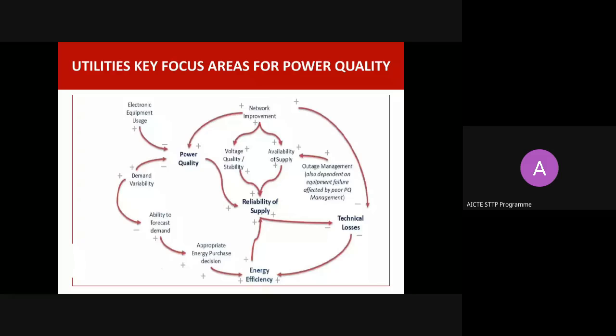There is transmission loss and distribution loss, put together as T&D loss. In current practice, we call it AT&C loss, aggregate technical and commercial loss. All the losses we are grouping into technical and commercial. In India, it is now less than 21%. In those days, it was more than 25%, 27%. On an average, it is about 21 to 23%. In Tamil Nadu, it is lesser than 21%. For the distribution company it is about 14%, and for the transmission company about 4%, put together over 18% for Tamil Nadu. All those losses can be reduced when you make improvements in the network. So this picture shows that network improvement has an impact on system reliability, power supply reliability and power quality.